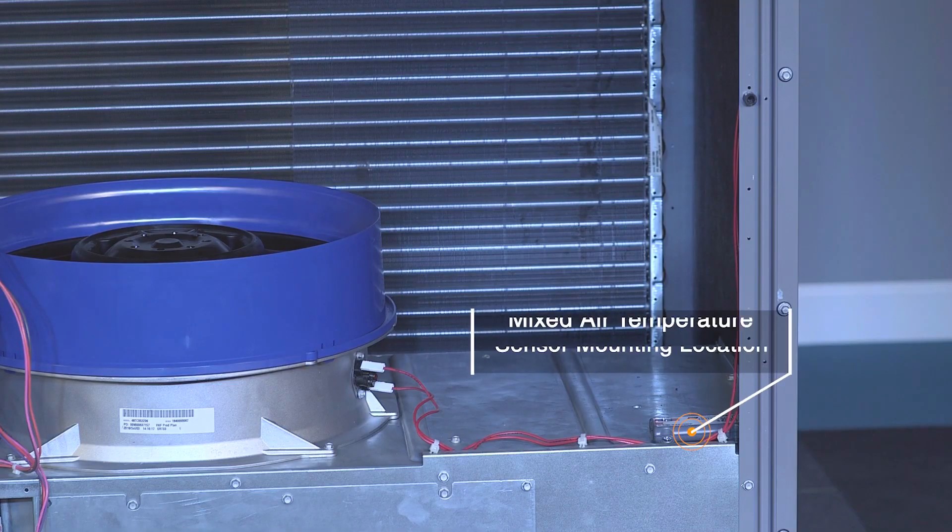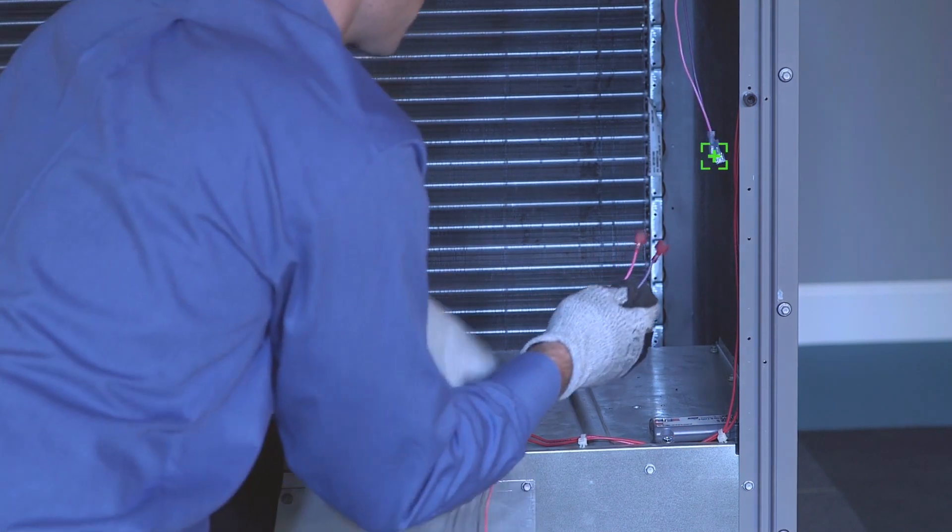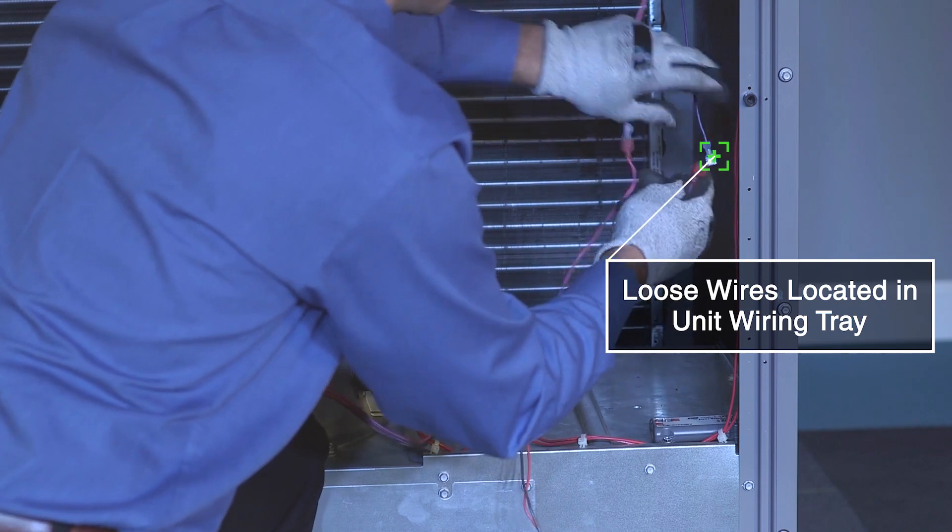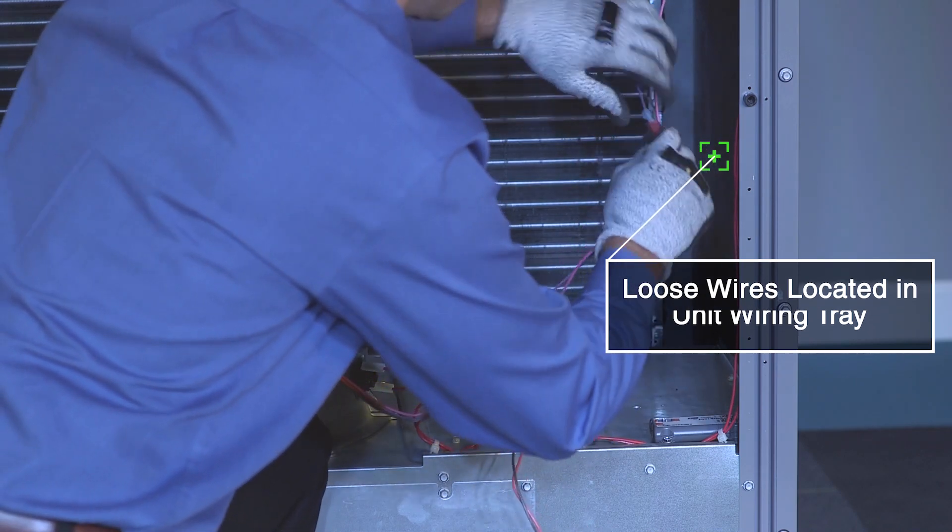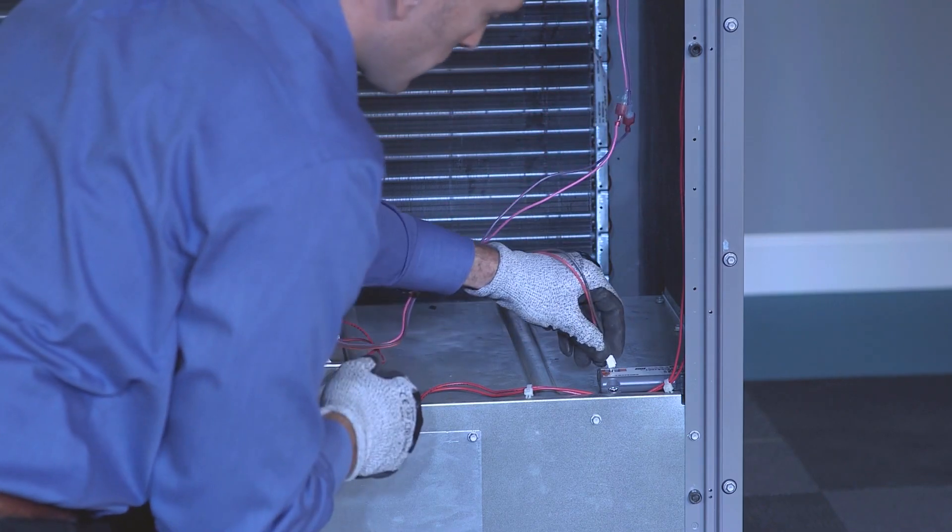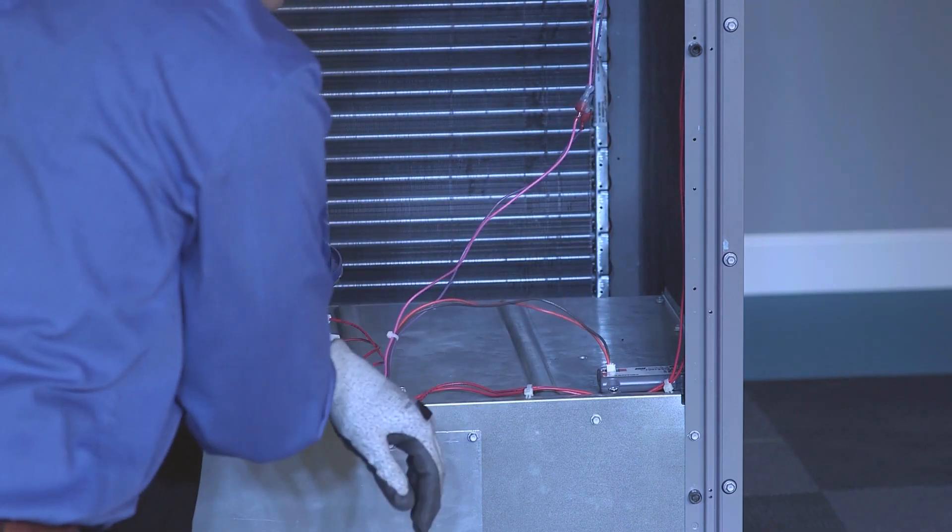Mount the mixed air sensor in the indoor blower section. Connect the pink and violet male quick connects from the four-wire harness to the pink and violet female quick connects that are loose in the indoor blower section. Connect the two-pin plug from the four-wire harness to the mixed air sensor.